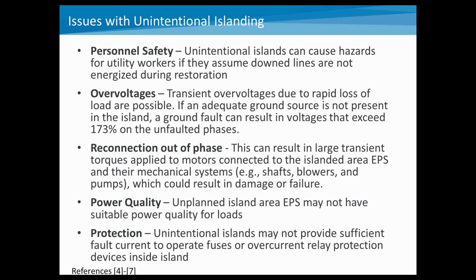In addition to that, there's also ground source issues. Ground faults can present and result in voltages that exceed 173% on unfaulted phases. So those are things that need to be addressed in terms of the grounding for distributed generation devices when you look at how you could create islands in those systems. Another issue is reconnection out of phase. One thing that could potentially cause an island is the opening of a breaker or a recloser. If you reconnect that system back to the grid, potentially the grid and the island are out of phase with each other, and that could cause a transient torque applied to the motors, which could result in damage or failure. So that is a potential issue.